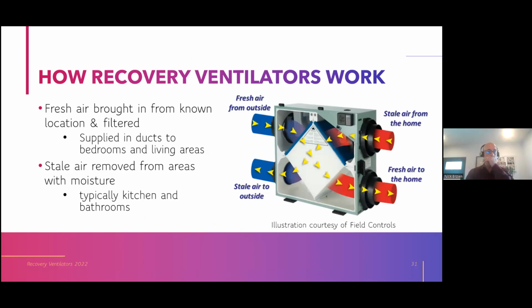So here's a zoom in on the unit itself. We're bringing in fresh air. We know the location we're bringing it in from, as opposed to exhaust ventilation. It's filtered, and most of these come with a really low grade filter just designed to catch insects. But I put a MERV 13 filter in the supply leg of mine. Not only is that Title 24 required, but it's a darn good idea, even if it weren't required, because it's going to pull out diesel particulates in the outside air, smoke particulates, etc.